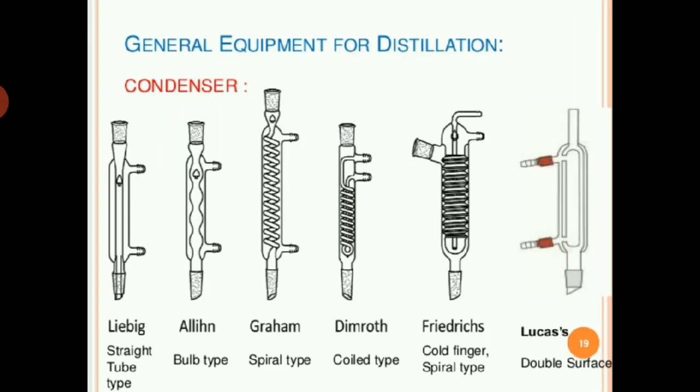The warm water in contact with the condensing surface must be quickly carried away and its place taken by fresh cold water. The cooling water is arranged to move on the counter current principle, that is, its direction of flow is opposite to that of the flow of vapor to be condensed.